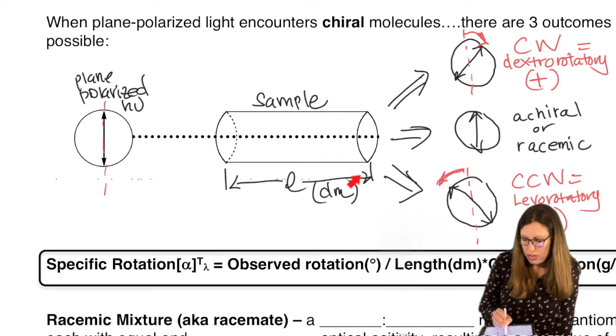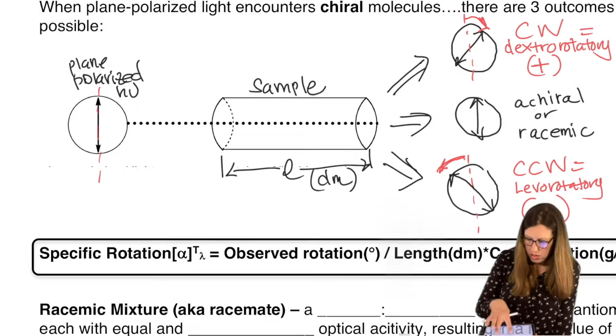Okay, so to get the actual specific rotation value, that's called alpha, we get the degrees of rotation, measured from here. So if this starts at 0, you can measure the degrees that it rotated. The length of the cell will vary with that. So just to be consistent, we include that in the calculation: the sample length that it has to travel through. And it also will vary with concentration. Much more concentrated will be different than very dilute. So the concentration is factored in, so that way you can get a consistent number across all samples.